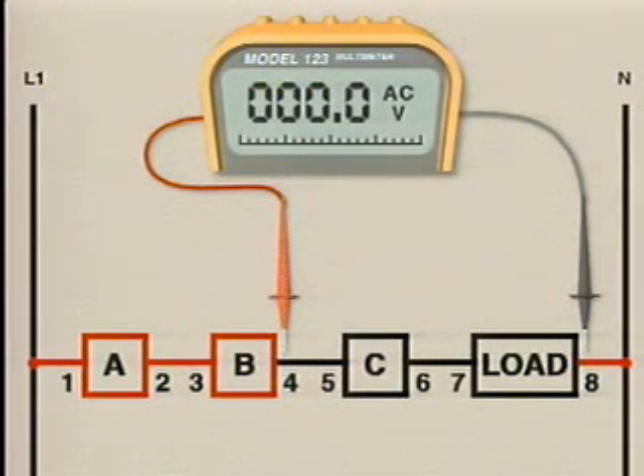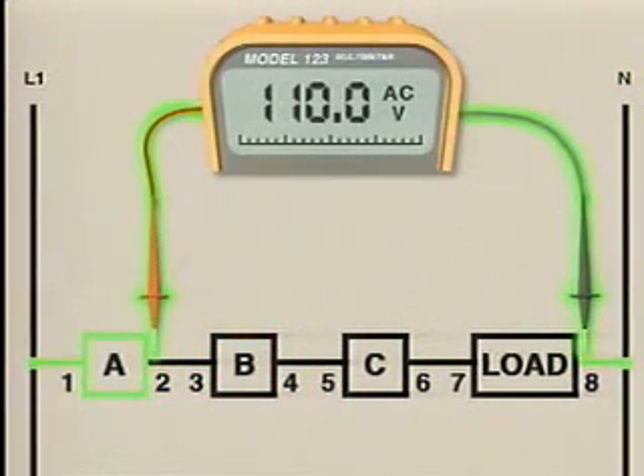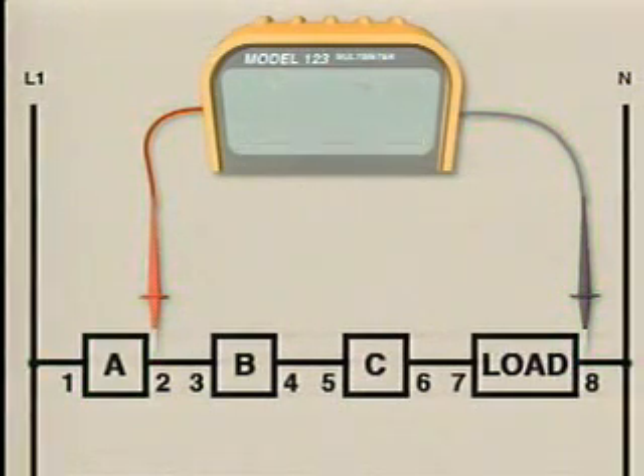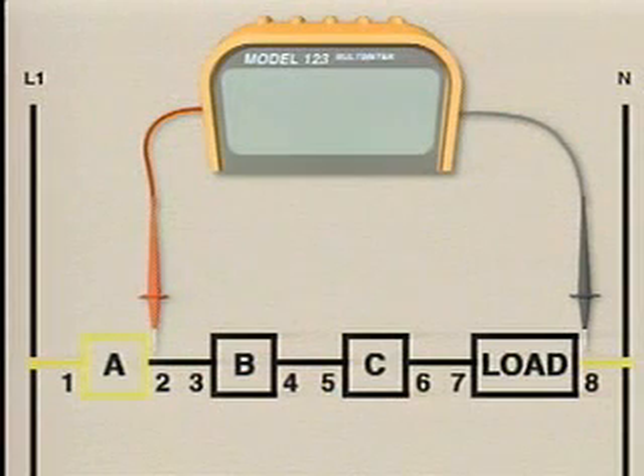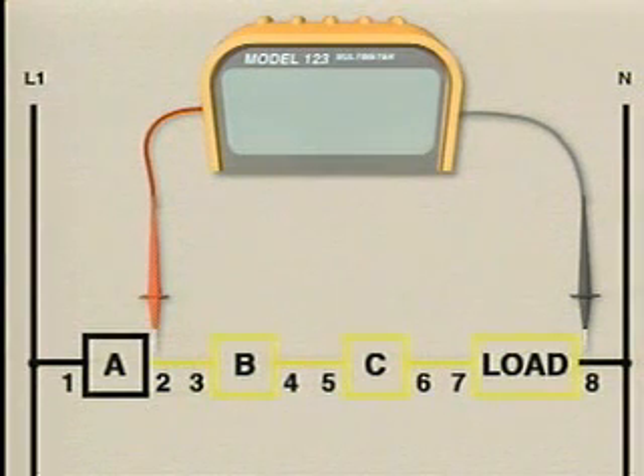It's important to note, though, that an indication of 0 volts could also mean that the test instrument has malfunctioned. The proper operation of the test instrument can be verified by using it to check a point where you already know there is voltage. Basically, each test that's made in a circuit eliminates all of the devices and wiring either within the test path or outside the test path, depending on the result of the test.